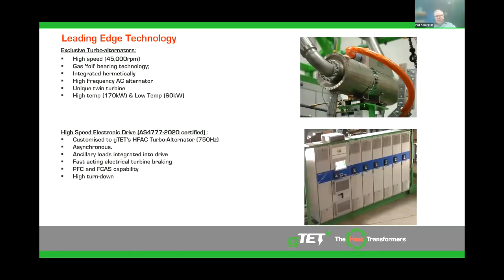GTET has developed some innovative high-performance ORC generator technology. We're one of a select few high-speed turbo machinery producers in the world using aerospace-derived gas foil bearing technology. Our integrated hermetically sealed permanent magnet turbo alternators operate at 45,000 RPM with electrical efficiency over 95% and turbine efficiency over 85%. The high rotational speed results in significant power for a relatively small package, such that our turbine is only 300 millimetres diameter and 600 millimetres long. And multiple turbo alternators are manifolded in parallel to produce up to a megawatt generator capacity.